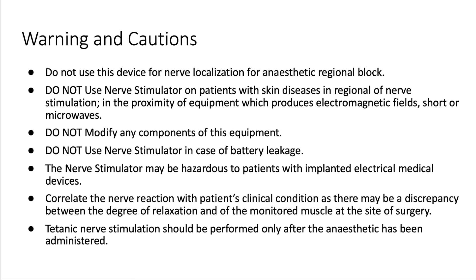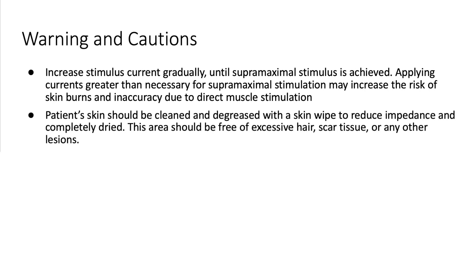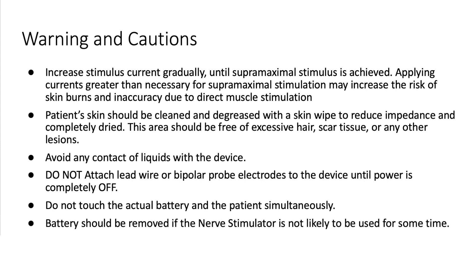Tetanic nerve stimulus should be performed only after the anaesthetic has been administered. Stimulus current must be increased gradually until supramaximal stimulus is achieved. Applying currents greater than necessary for supramaximal stimulation may increase the risk of skin burns and inaccuracy due to direct muscle stimulation. Before use, the patient's skin should be cleaned and degreased with a skin wipe to reduce impedance and completely dried. This area should be free of excessive hair, scar tissue or any other lesions. Avoid any contact of liquids with the device. Do not attach lead wires or bipolar probe electrodes to the device until the power is completely off. Do not touch the actual battery and the patient simultaneously. Battery should be removed if the nerve stimulator is not likely to be used for some time.